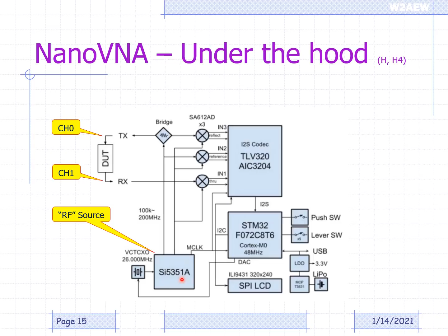So under the hood of the H and the H4, this is what it looks like from a block diagram schematic standpoint. Channel 0, channel 1, that's effectively port 1, port 2 in VNA parlance, where your DUT gets connected. The RF source is this serial bus controlled RF synthesizer, an SI5351. A bridge is used to separate out the transmitted and reflected signals, so that when we have an impedance mismatch, we'll get the reflected signal coming back.